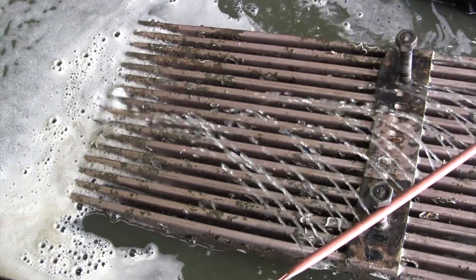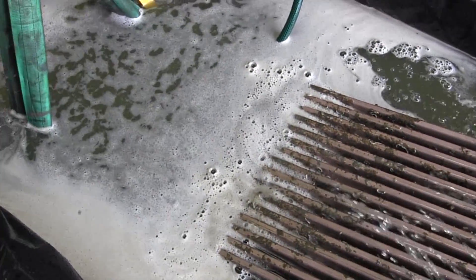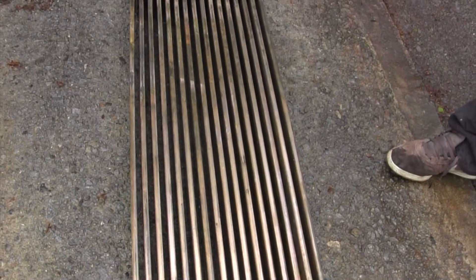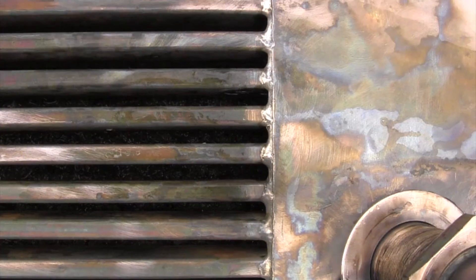The keel cooler heat exchanger was cleaned using a mix of 50-50 dynamic descaler to water for a period of 5 hours. After the cleaned keel cooler was rinsed to remove any surface residue, you can see that the heat exchanger tubes have been returned to an as-new condition.